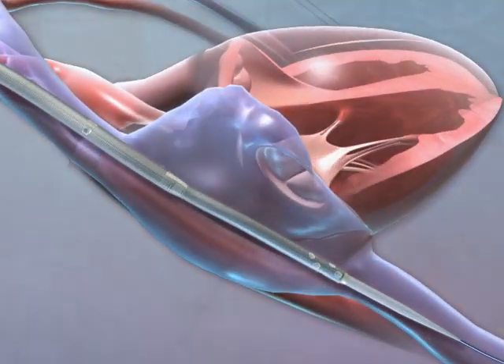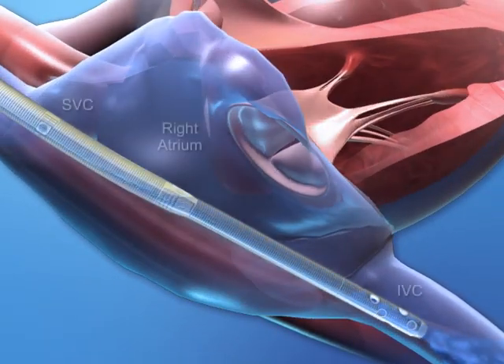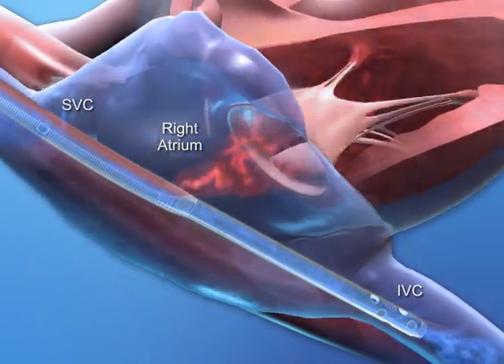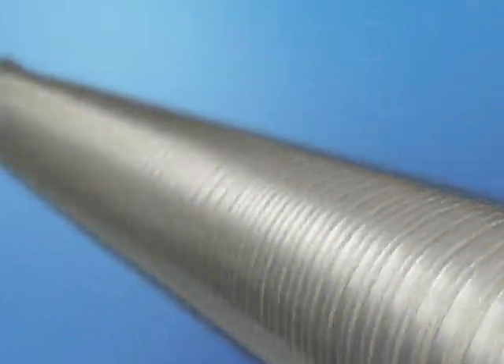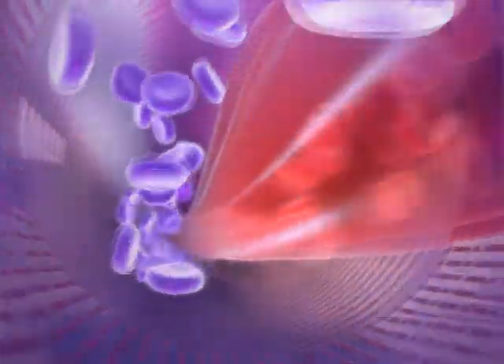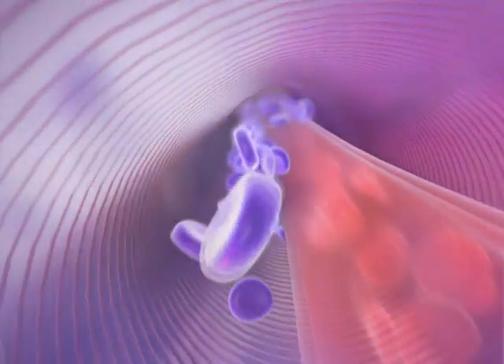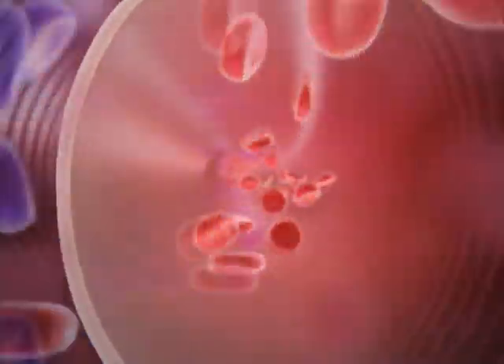Upper and lower drainage holes are located in the superior and inferior vena cava, and blood return from the external circuit exits the catheter in the right atrium. With its unique bicaval design, the catheter matches the body's natural flow ratios by simultaneously balancing the removal of deoxygenated blue blood and the return of oxygenated red blood, thus maximizing drainage and minimizing recirculation.